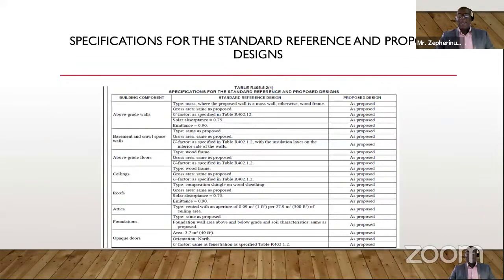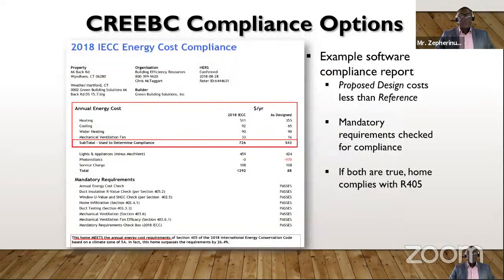And at the end of the day, the annual energy cost of the standard design must be equal to the annual energy cost of the proposed design. So if the annual energy cost is the same or less, then your design would meet the code requirements and be approved by the code officials. This is just an example to show you how you compare the annual energy cost based on the standard design and your proposed design. So you have to be lower than the standard. So in this instance, this application would meet the requirements of the code.